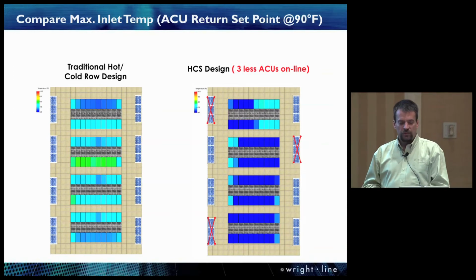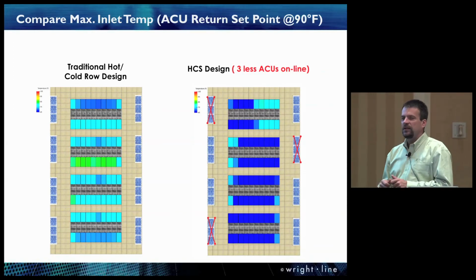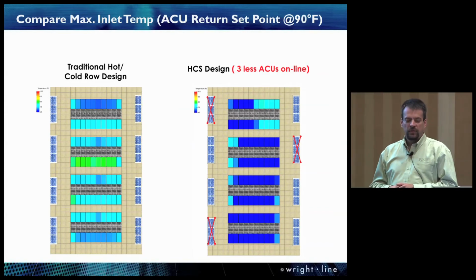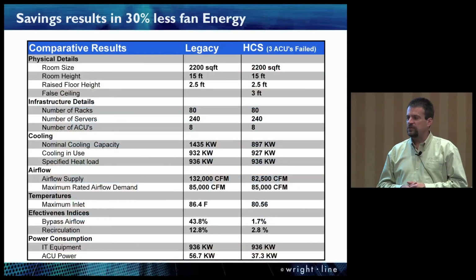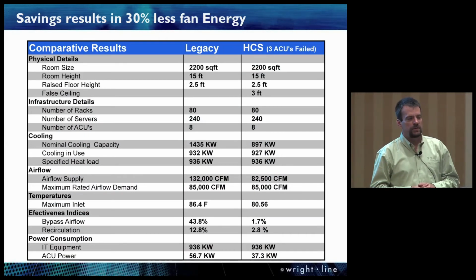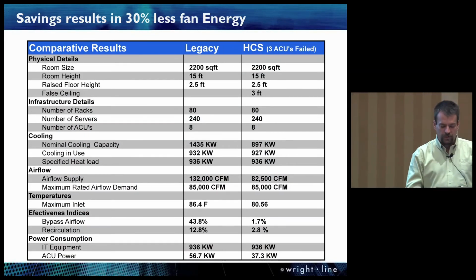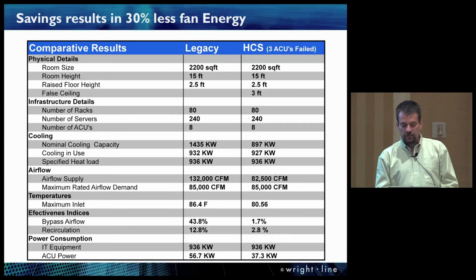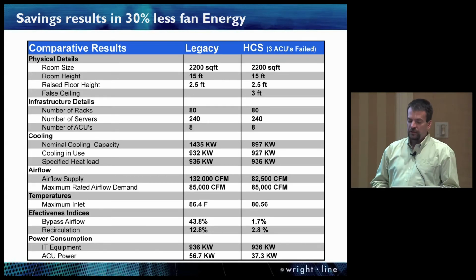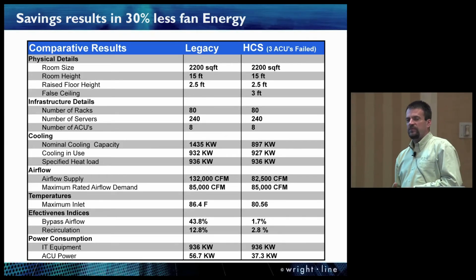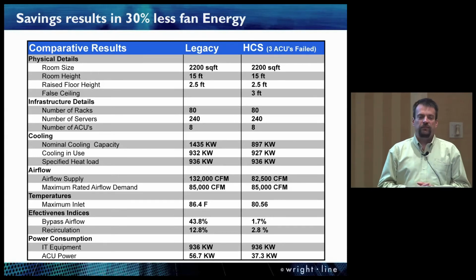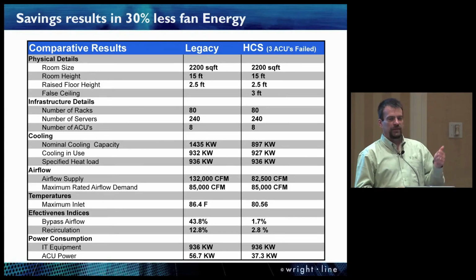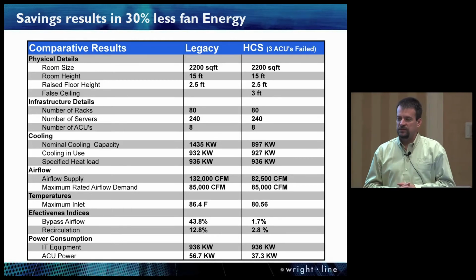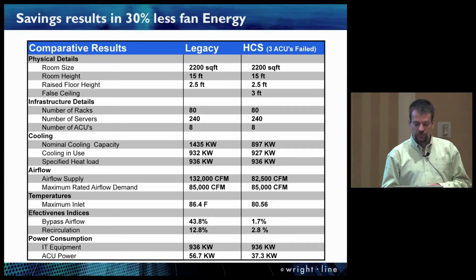As I really start to peel the onion and look at the actual attributes and the values, the legacy design versus the heat containment or the chimney type design, there are some important points. Really the number one thing that we want to look at is these numbers here. This is the airflow supply and the demand. In the legacy unit, 132,000 CFM of supply, and I'm getting 85,000 CFM of demand, meaning the IT equipment is saying, give me 85,000 CFM and keep it within ASHRAE limits.